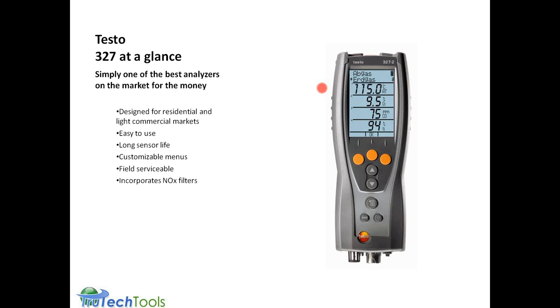It incorporates NOx filters. I believe we have a slide covering why that's important, but just the basic overview is, if you remember, recall back to the slide where we talked about all those toxic gases coming out of the combustion system, nitric oxide gas is one of those toxic gases. It will actually trick a CO sensor into believing it is carbon monoxide gas to a certain extent. You need about 10 parts per million of NOx. It'll look like between 20 and 50 parts per million CO.